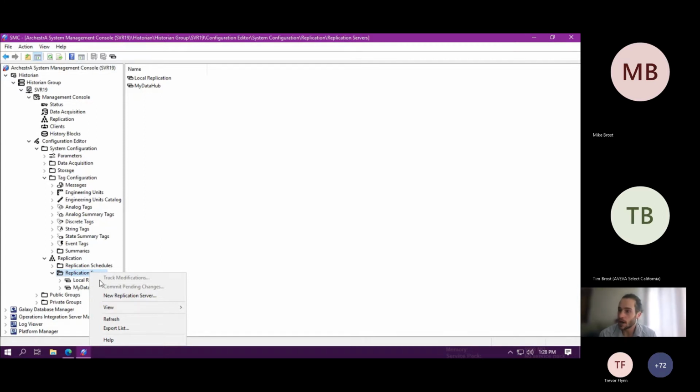But the new Historian to PI replication feature can really help enable infrastructures where the AVEVA Historian gathers data on the SCADA network in a tier 1 configuration and shares data to the PI server that sits on the enterprise network in a tier 2 configuration. You can currently do that with a tier 1 and tier 2 Historian, but with PI, you can instead leverage the tools of Pi and place it on your enterprise level to unlock more capabilities. And we'll explore those capabilities in a second. But this process basically strengthens your data security and data fidelity while allowing you to segregate both systems.